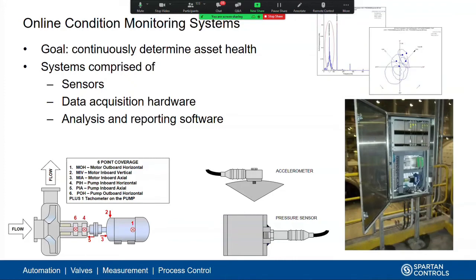Layered on top of that, we have an interface from that data acquisition hardware to dedicated software applications that analysts can use to interpret the results. The hardware converts raw signals into usable vibration measurements, and the analysts use that data to interpret exactly what the fault condition is. Do we have a bearing fault? An alignment fault? A looseness fault? All these things can be interpreted by looking at the data.